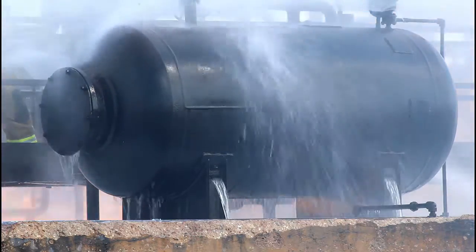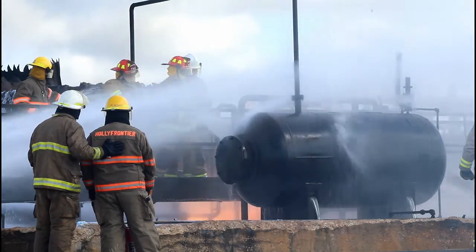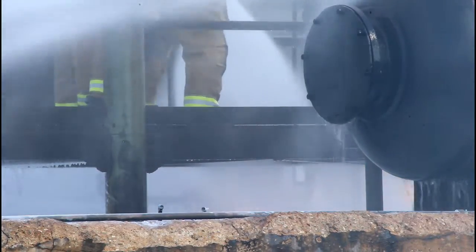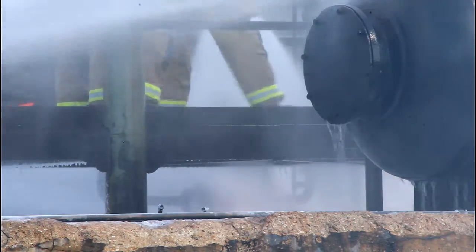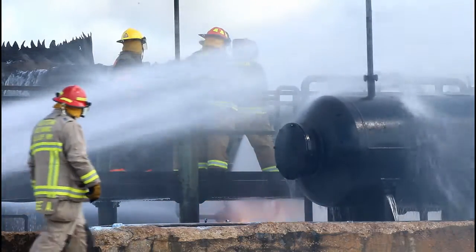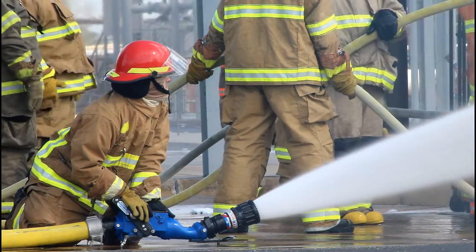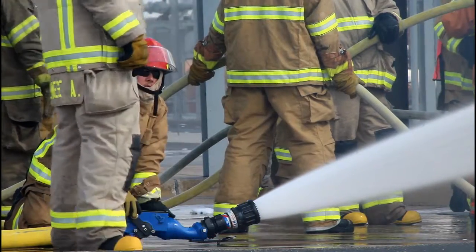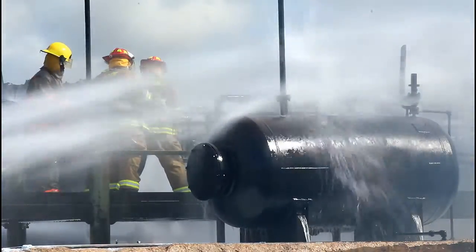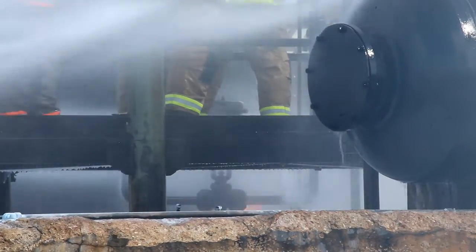When you grab an eductor, don't assume it's 95 GPM — it could be 25 or there's a 60 in there as well. There's also a JS-6, which flows 60 gallons per minute, not 95. Most have gone off-site but we've had both a JS-6 and a JS-10 here before. Also note the hose connects with a little dot — just twist the top and you can go down to half percent or quarter percent, but we're using one percent training foam.